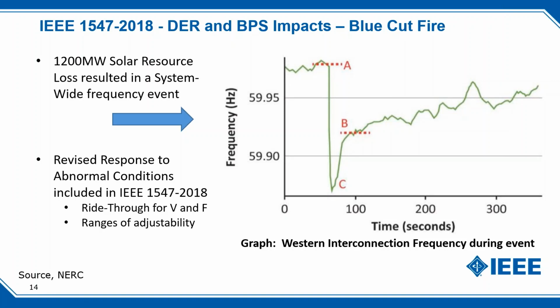The implications of this is that we revised the requirements for inverters and the response to abnormal conditions to include ride-through requirements for voltage and frequency, with a lot of adjustability to allow for different regions to accommodate different needs based on their circuit and penetration of DER.